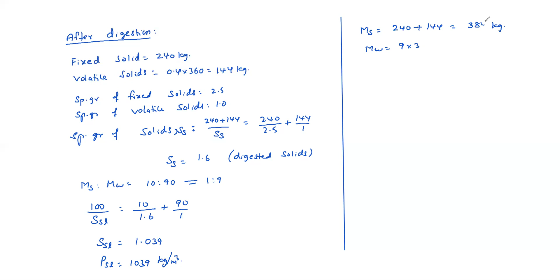Volume of sludge equals mass of sludge by density of sludge, 3840 by 1039, which is 3.7 meter cube. So he's asking us to find the sludge volume before and after, and also the percentage reduction. Initially it was 11.26, now it is 3.7. Percentage reduction is 11.26 minus 3.7, by 11.26, into 100, which is 67.1%. The volume is reduced by 67.1% after digestion.